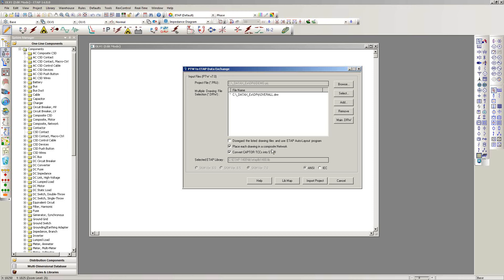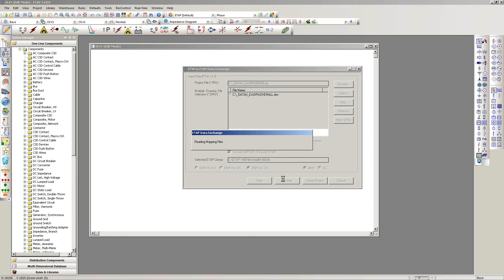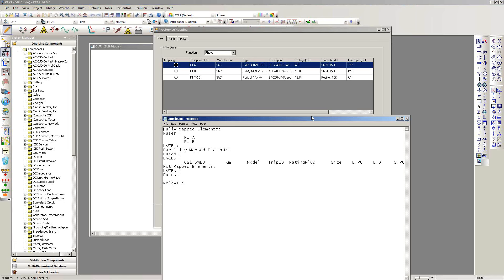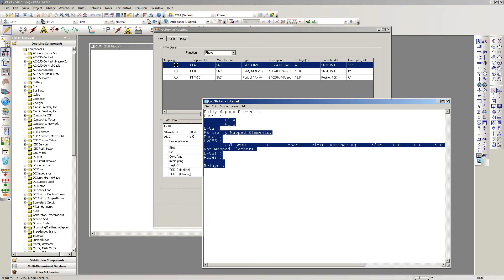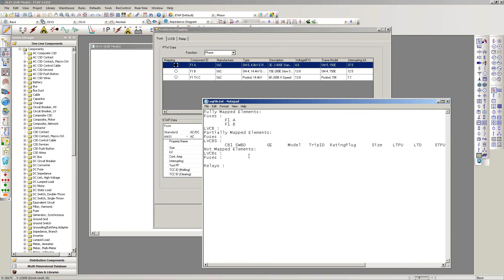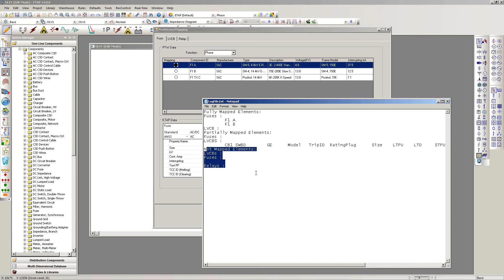I'll also check the option 'Place each drawing into a composite network,' so that each one-line diagram gets imported into a composite network. The next step is to import and map all protective device settings into an ETAP equivalent library. When I click on 'LIB Map,' the library map interface is automatically called, and the first thing you see is a log file — a text file that tells you which elements have been fully mapped, partially mapped, or not mapped. In this case, I have one circuit breaker that has been partially mapped and everything else is fully mapped.